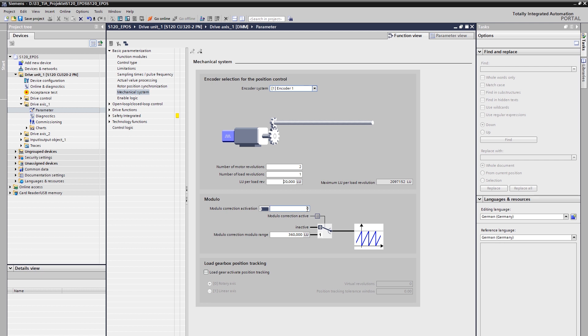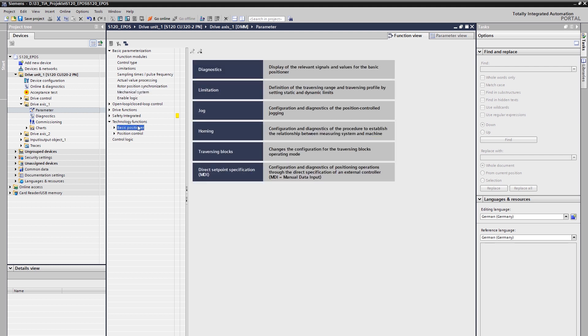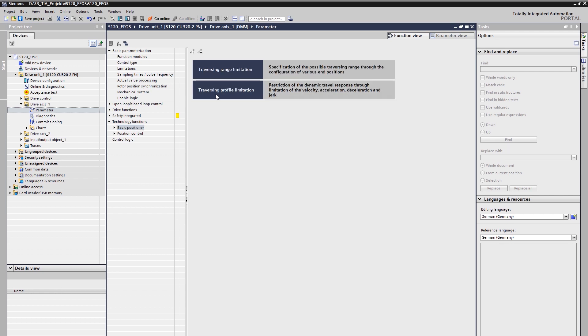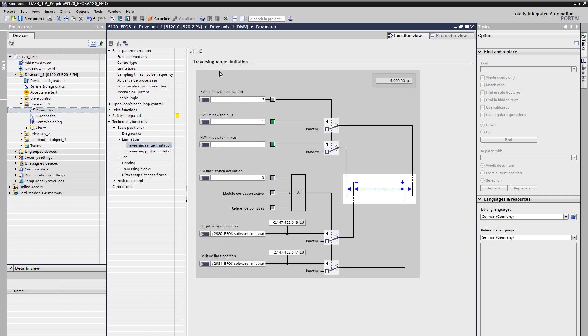The adjustment of the mechanics is now completed. The configuration of the basic positioner can be found under technology functions of the function view. This is where the clear diagnosis of the basic positioner, its limitations and the individual operating modes are located. In the first step, the parameterization of the limits is carried out. There are two options available below the travel range limitation: hardware limit switches and software limit switches. Especially for linear axes, such limit switches are necessary.